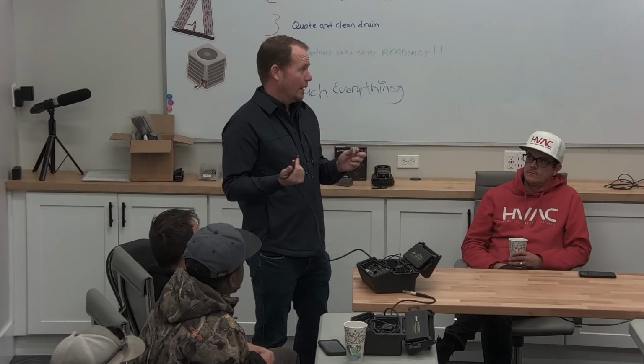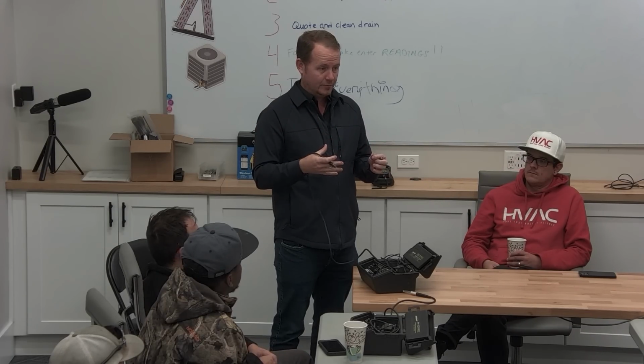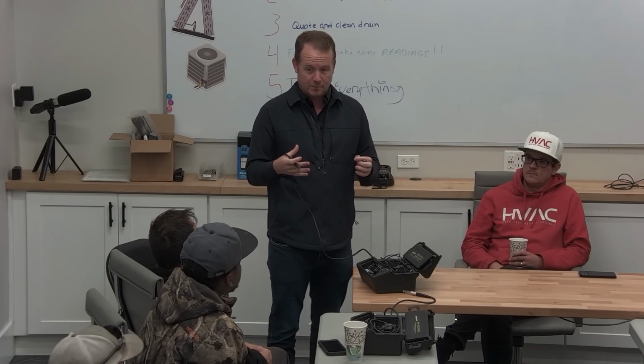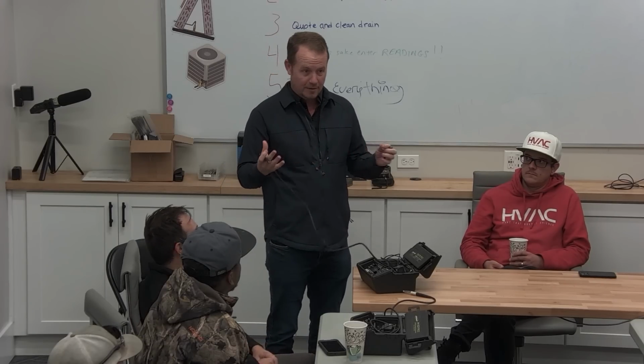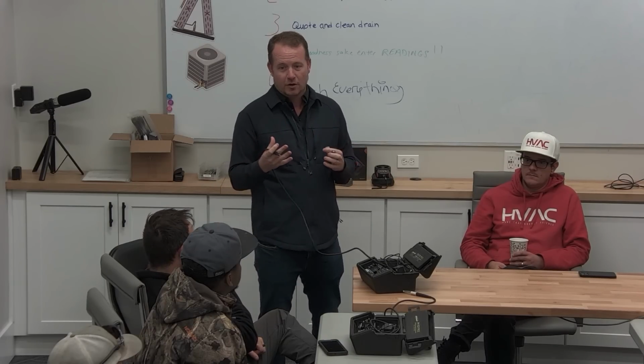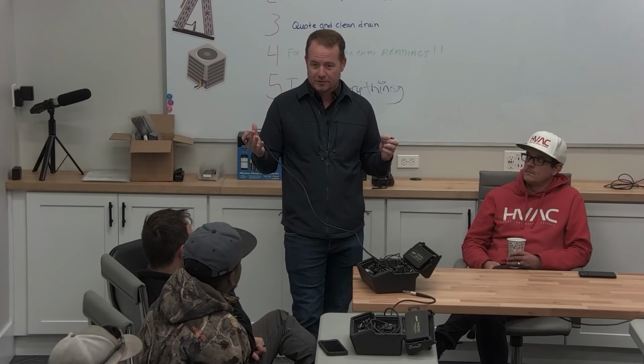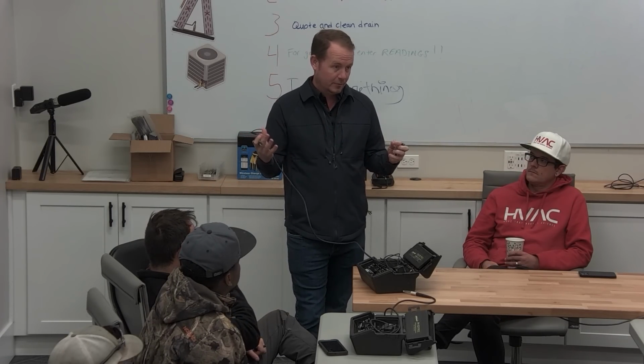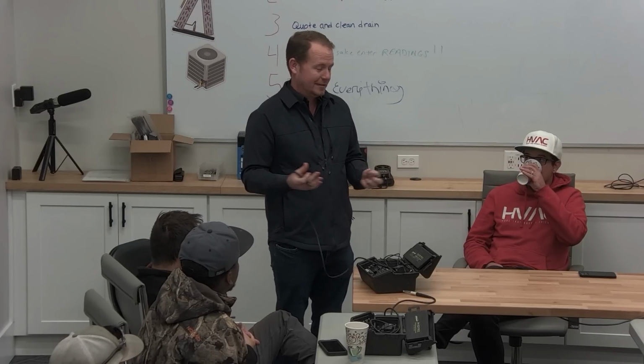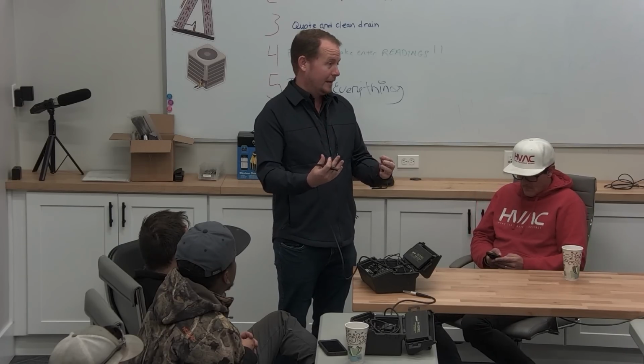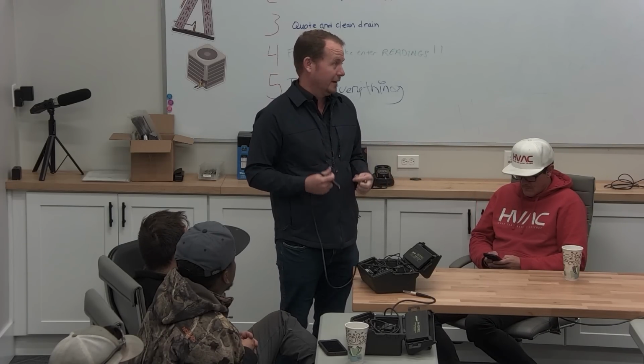But we have a secret weapon, which is a vacuum chamber - we have at least one, probably a couple. If you put electronics in a vacuum chamber and pull a vacuum on it, the moisture evaporates, it boils off - that's what we do inside of the system. So we have this magic electronics-fixing device available to us, it's on all of your trucks, called a vacuum pump, and all you need is the vacuum chamber. We can get more of them if you guys get used to using them. If you get a meter that gets wet and it's not working right, get the batteries out of it, let it dry, but if you can get back here, or have a few minutes during a meeting, just throw it in the vacuum chamber and pull a vacuum on it.